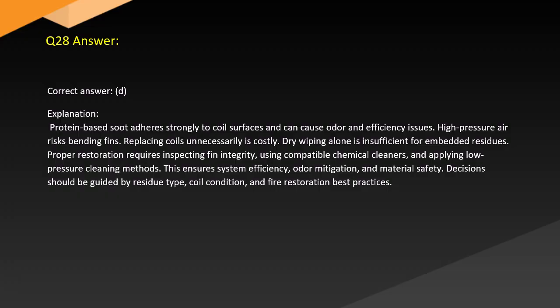Answer. Correct answer: D. Explanation. Protein-based soot adheres strongly to coil surfaces and can cause odor and efficiency issues. High-pressure air risks bending fins. Replacing coils unnecessarily is costly. Dry wiping alone is insufficient for embedded residues. Proper restoration requires inspecting fin integrity, using compatible chemical cleaners, and applying low-pressure cleaning methods. This ensures system efficiency, odor mitigation, and material safety. Decisions should be guided by residue type, coil condition, and fire restoration best practices.